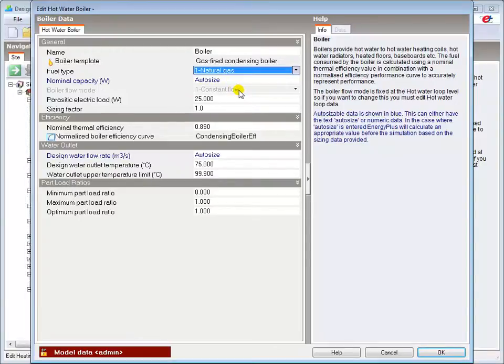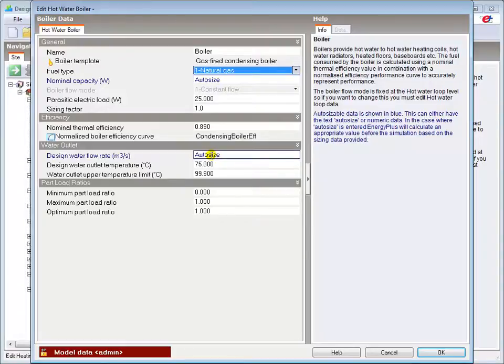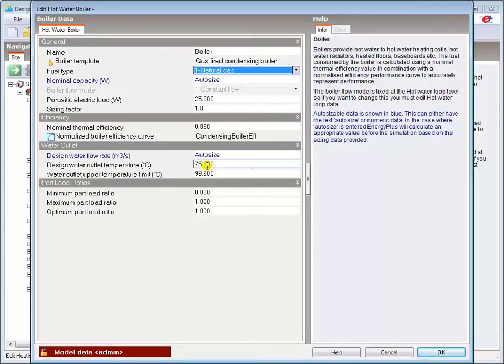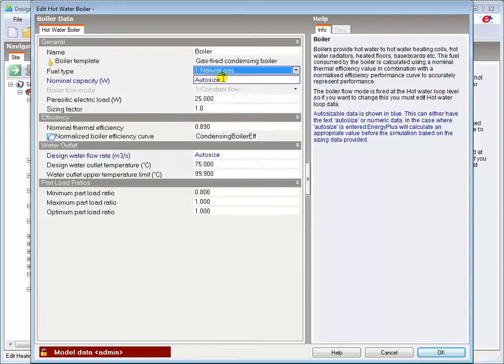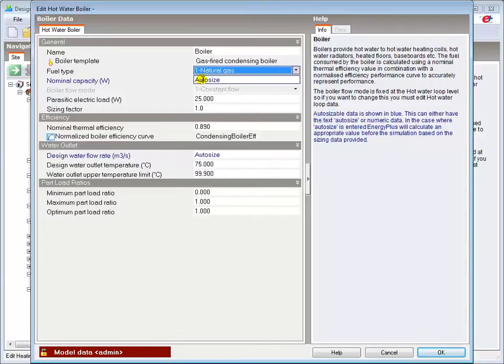Note that there are two auto-sized values in this particular dialog. The Design Water Flow Rate is combined with the Design Water Outlet Temperature to meet the boiler's nominal or maximum rated capacity here. Where you have more than one auto-sizeable option for a component, you should either use Auto Size or input manual data consistently. You shouldn't auto-size one and manually size the other in this dialog, for example.